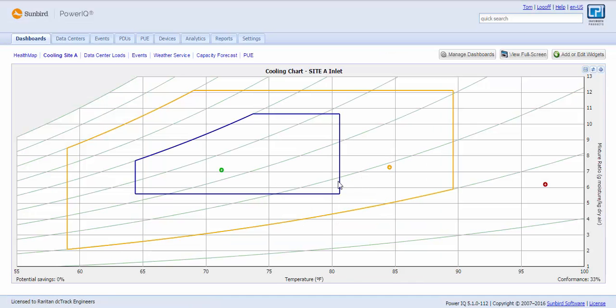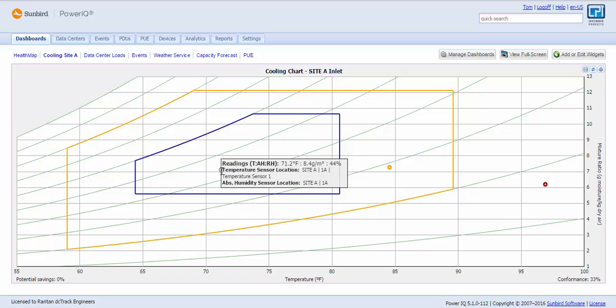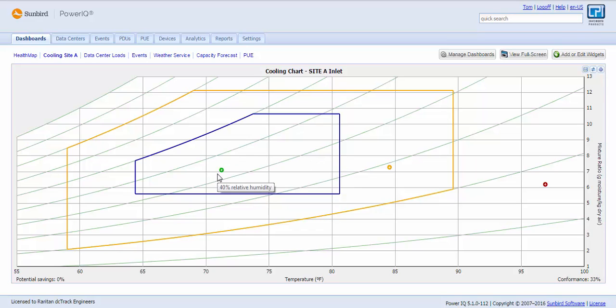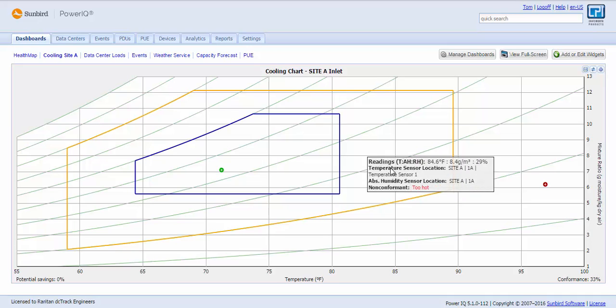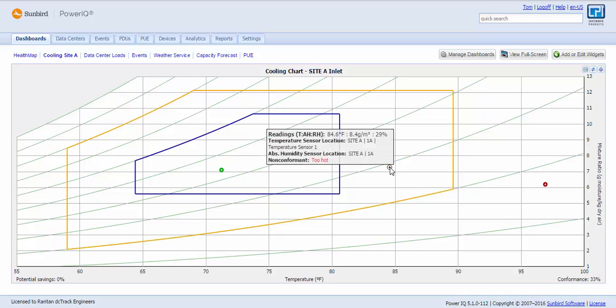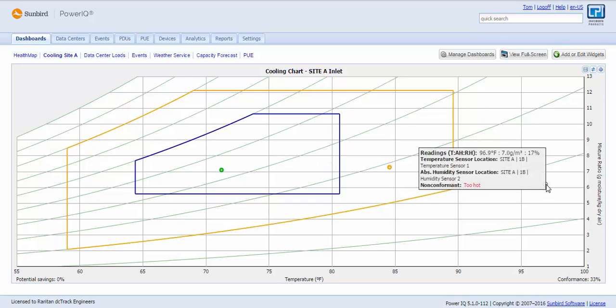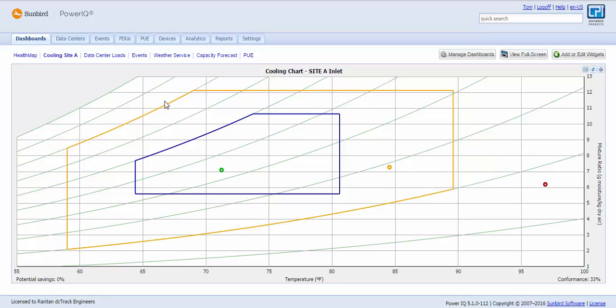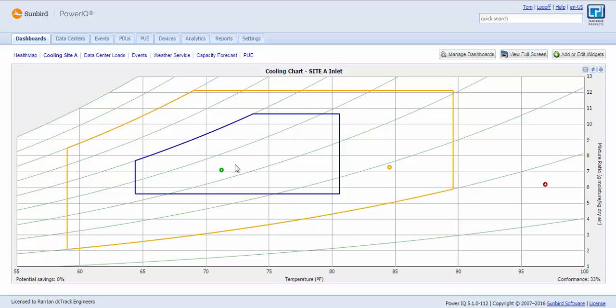This provides the blue line is the recommended range, so if a sensor humidity pair is within the blue line, in this particular case 71.2 degrees and 44% humidity is within the recommended range, the sensor pair is green and counts towards my conformance index. If a sensor pair is outside of the recommended range but within the allowable range, then it's yellow, and we give an easy indication of the non-conformance. In this particular case, it's too hot, and if it's outside the allowable range, then it's red. This allowable range allows customers to operate in greater envelopes for free cooling because they're certifying that their equipment can handle the more extreme conditions that ASHRAE has specified as an allowable range based upon the class of equipment. If all your sensor pairs are within the recommended range, then we'll estimate your savings.